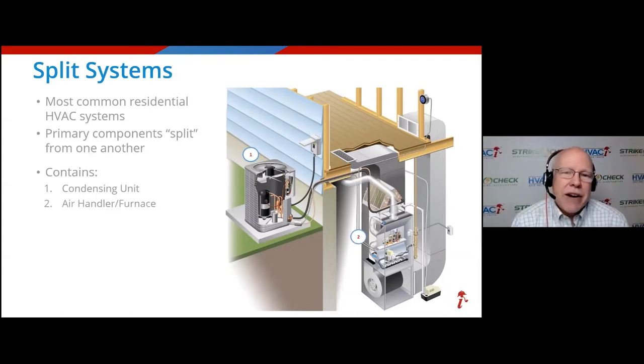On the inside, we have an air handler or furnace. That terminology gets a little confused sometimes, so I'll see if I can break it down a little bit for you. In our diagram, we see an upflow furnace. It's standing vertically, and that would be in a basement, a closet, maybe the garage. It has all those components in the middle by that number two that are capable of generating heat. You're probably burning a fuel like natural gas, that's the most common. You have an exhaust flue, you have heat exchangers. At that point, we're going to call that a furnace because it's generating heat.